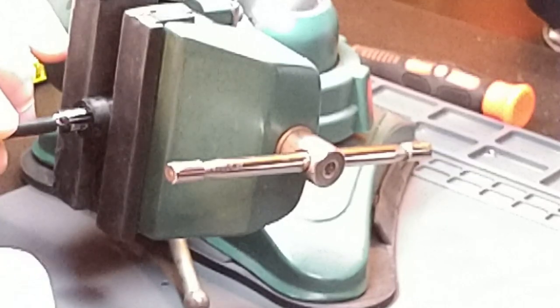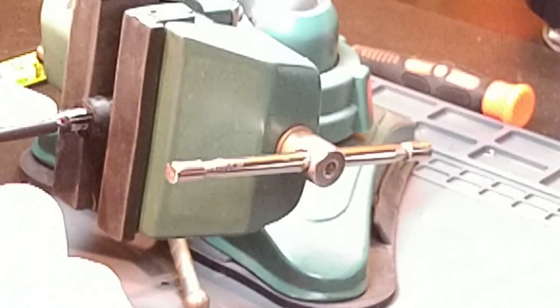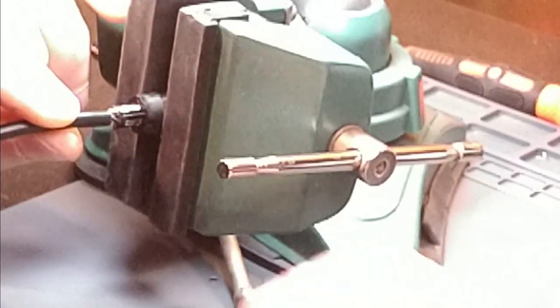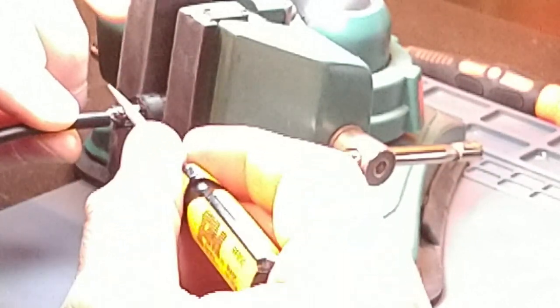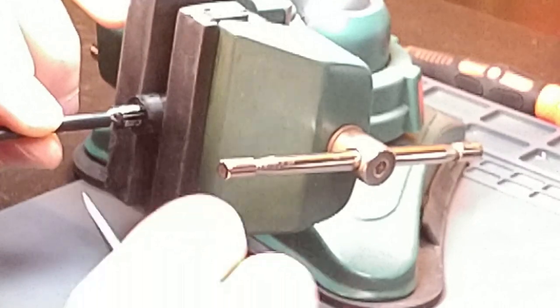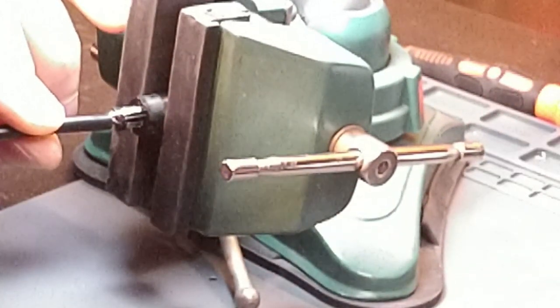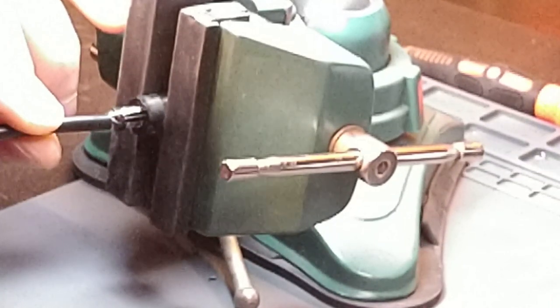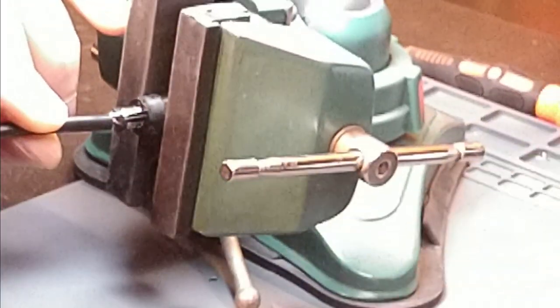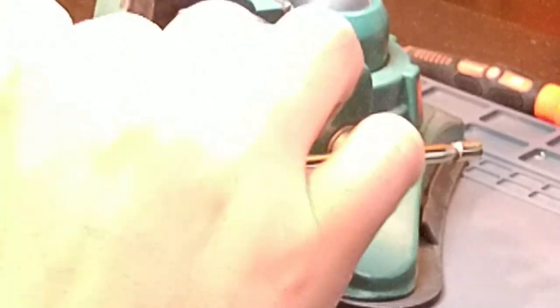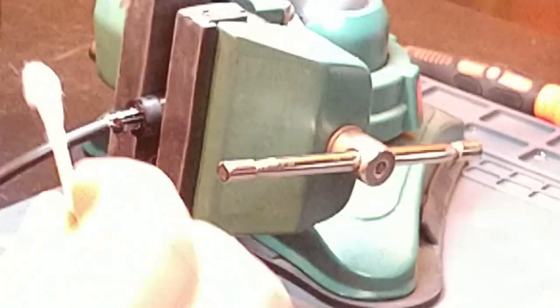We're going to do our drain now. And this is where you want to be careful, because our drain is very thin here. A lot of guys realize that after the fact. If you've never worked with shielded cable before, you're in for a treat. The idea is, as I go to do this, you want to make sure that not only that lead is coming in, and preferably as straight as possible, you don't want stress on it. What you want to do is, I always find that just folding it down. That's why we left, we actually tin just the top and not the bottom. We got a much easier way to put less stress on that braid. Now everything is basically set there. Here we go. Now you're done.